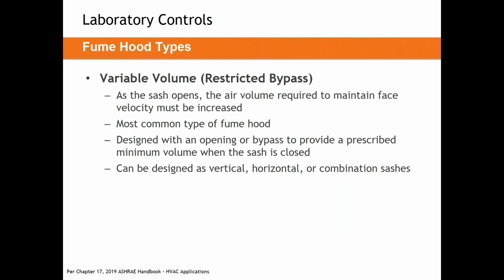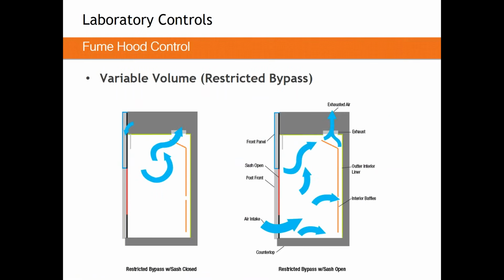Any time your fume hood, when it's open, will increase your makeup air number, for example, if your air change rate is 6 and your thermal load is extremely low, and when your fume hood opens it would consume 2,000 CFM but you only needed 1,100, that is a good reason to use a variable volume fume hood, which we'll introduce here. So with a VAV hood, we'll skip past the text and just show the image here. Basically, there's no open bypass. There may be a small restricted bypass to always ensure some air flows into the hood, but it's not a big open bypass. So as the sash opens, we need to provide proportionally more airflow.